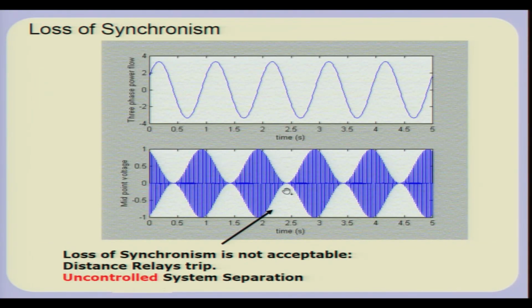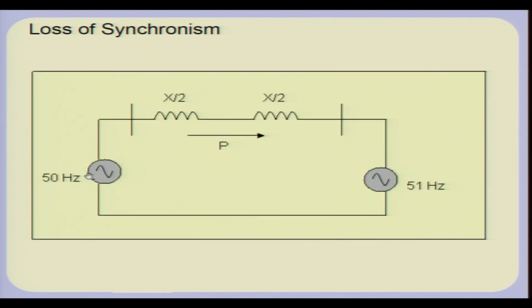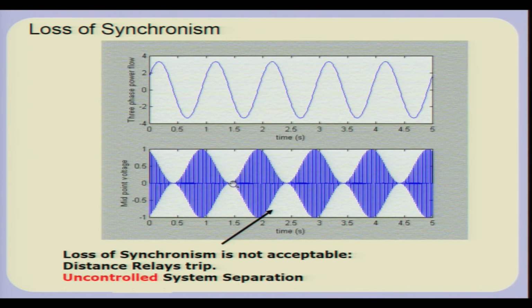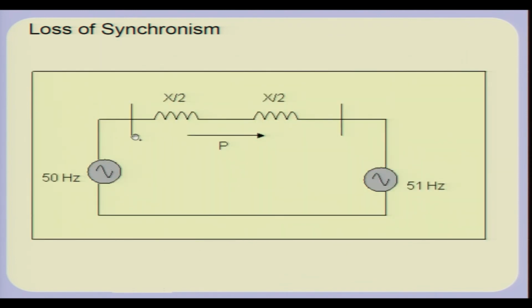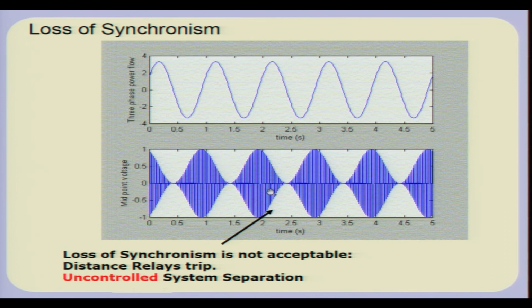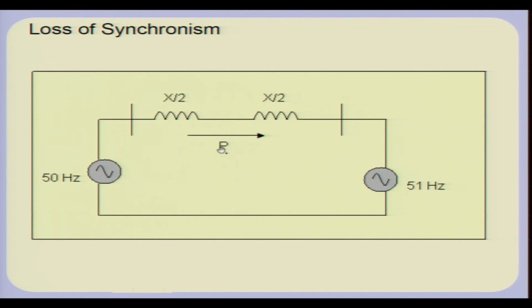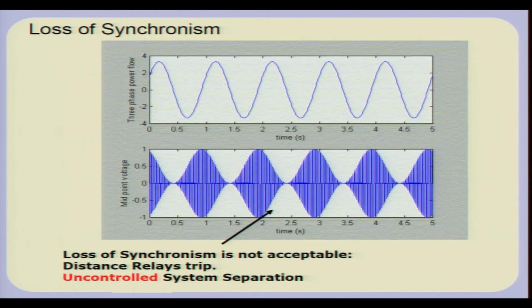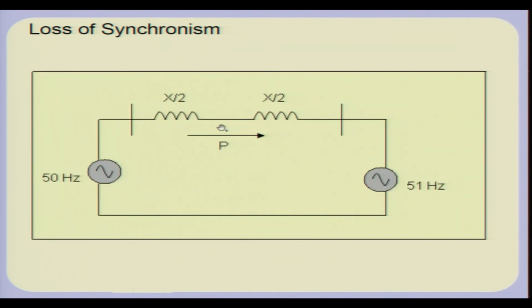And if you look at the midpoint voltage here, it is a 50 hertz system, but because one is at 50 and the other is at 51, the voltage at the midpoint shows beats. So, you can't operate this way, because your voltage magnitudes would keep fluctuating and power flows would keep changing. If power flows are changing, the torques on the machine will also fluctuate quite wildly. This will damage the equipment. The voltage will also fluctuate wildly, and therefore you would need to trip. In fact, because the voltage at the midpoint can become 0 due to these beats, distance relays may think that this is a fault, and they trip, and because of that these two systems undergo a natural separation.